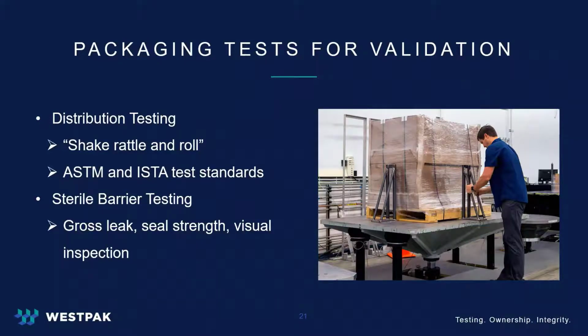The second group of test types are sterile barrier tests. The majority of medical devices are sterilized prior to use in order to prevent patient infection. Sterile barrier testing will ensure that the sterile barrier remains intact and the devices are able to be used without risk of infection. These tests may include gross leak testing, seal strength testing, as well as visual inspections.